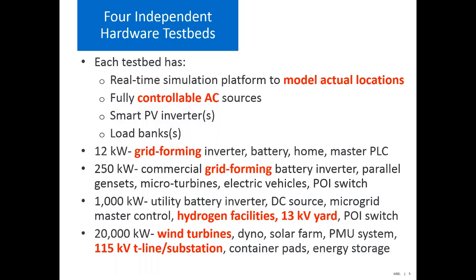features to them. So the smaller one, for example, does have a grid forming inverter, but it's single phase, more in tune for residential type research, whereas the hundreds of kilowatts and up all have three-phase, typical commercial scale voltages, 480 volt nominal usually. Once it's been converted through the inverters, it typically puts out 300 something volts, and then there's an isolation transformer to get me to 480.